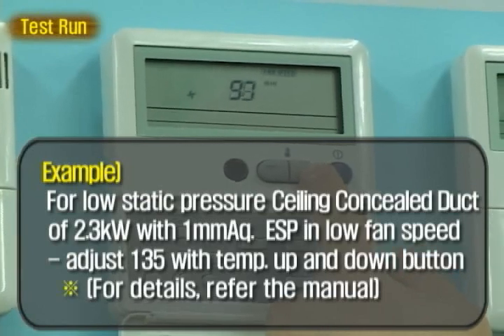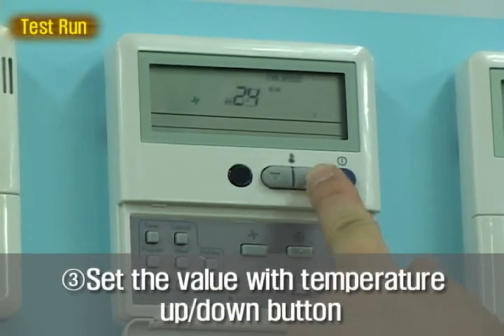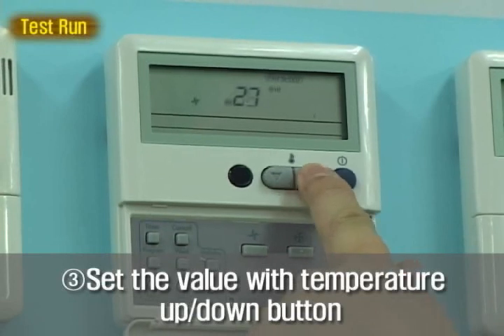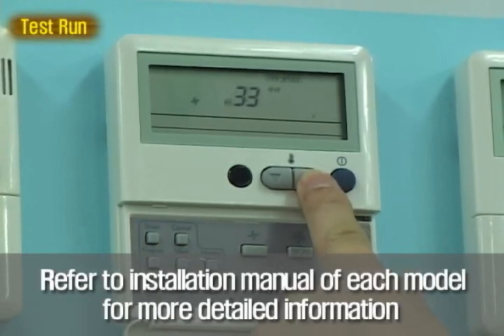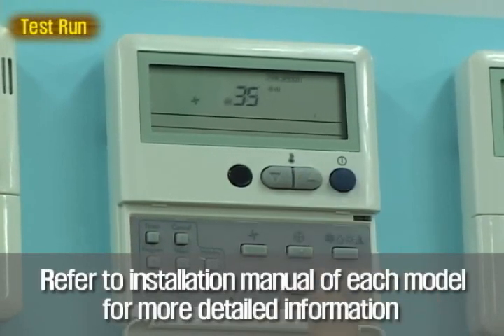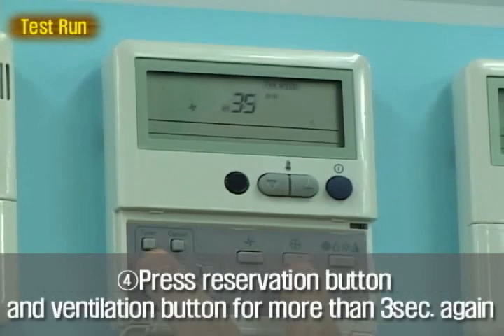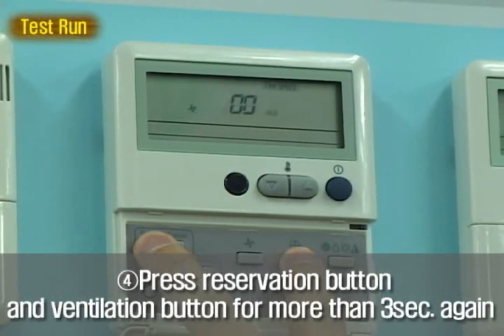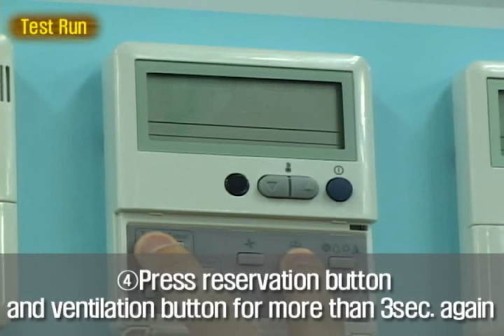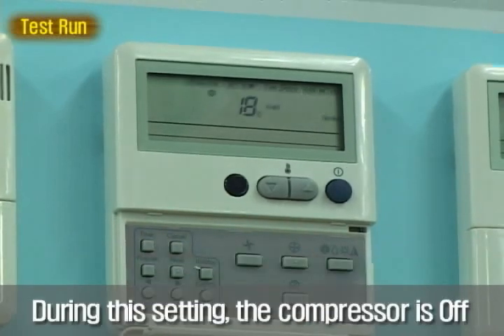For example, for the low static Ceiling Concealed Duct with 1 mm of static pressure in low air speed, set the value to 135 by pressing the temperature up and down. And press Reservation button for more than 3 seconds to save the data. During this setting, the compressor is off to protect the product.